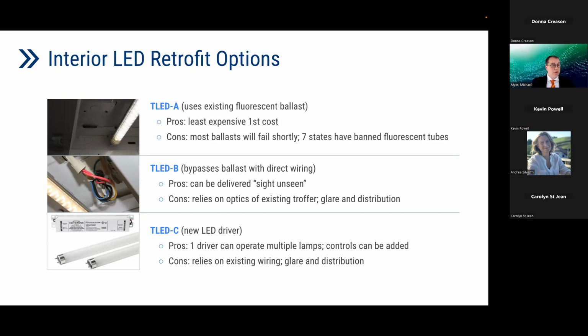A recent example I know of: somebody accidentally replaced a type A TLED on a fixture that had already been rewired for type B, and it caused a major electrical short and melted the end cap of the type A TLED.